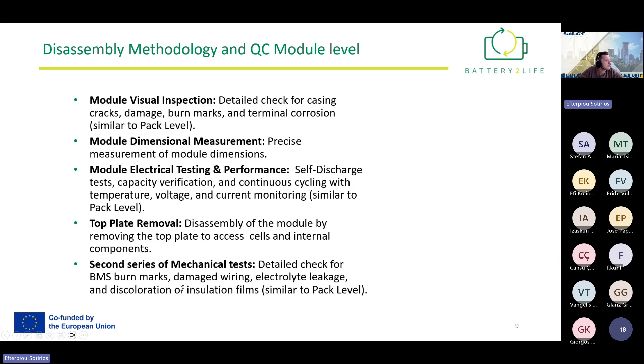After that, we remove the BMS of the slave unit inside the modules, and inspect for cell swelling, terminal corrosion, and burn marks. Then again, electrical testing: measurement of open circuit voltage of the cells, and evaluation of AC internal resistance and DC internal resistance.